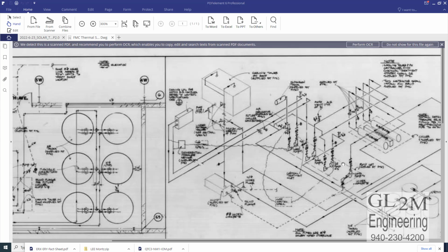There are a few elements in just about every pump design. You'll see these are flex connectors here. This is a triple duty valve. A triple duty valve on the discharge of a pump is an essential ingredient. It serves 3 purposes, as the name implies. It serves as a check valve, a balancing valve, and a stop valve. And so if a pump is not needed, it prevents water from flowing backwards into that pump. And that's essential because if you start that pump while it is flowing backwards, you'll likely break the pump.